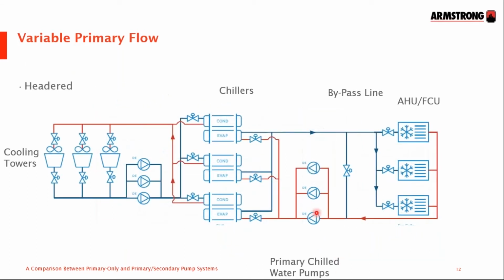Right. The alternative, of course, is headered pumps. What you're seeing now is the same as before, except the pumps are now headered together and will be operating in parallel. This provides greater redundancy. If any one pump goes down, any of the other two pumps can handle any of the three chillers showing there.